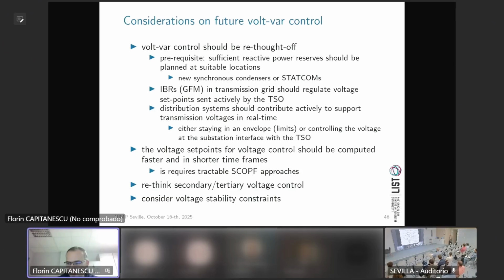Yeah, thanks a lot for the question. I agree that power electronics can do amazing things. The main issue regarding the technology itself is that the converters were designed with the mindset to produce only active power. For that reason, the biggest issue is: if you take the same rated power, so MVA, and look into a synchronous generator, how much it can produce or absorb reactive power based on this MVA, you find that in active production they could go to 80% of the capacity, and in absorption maybe 60%.